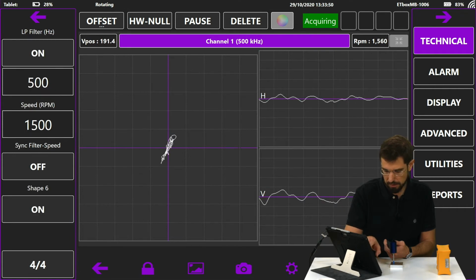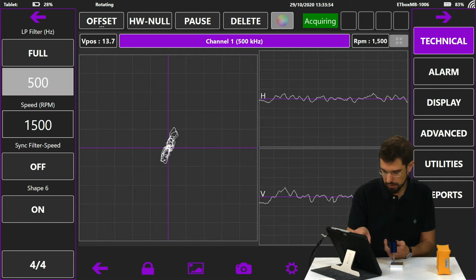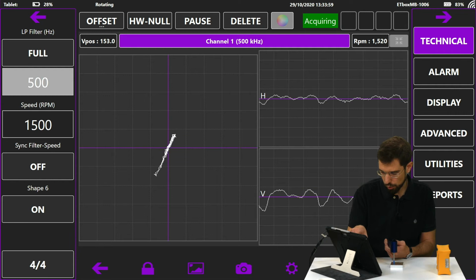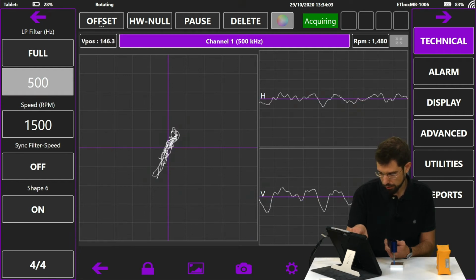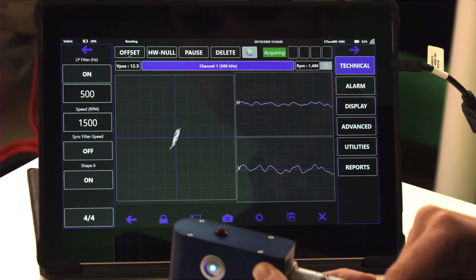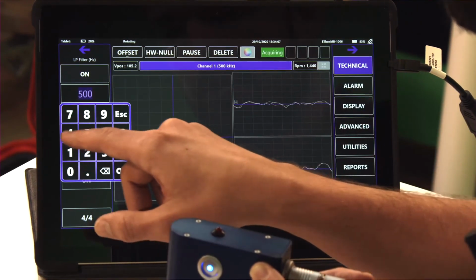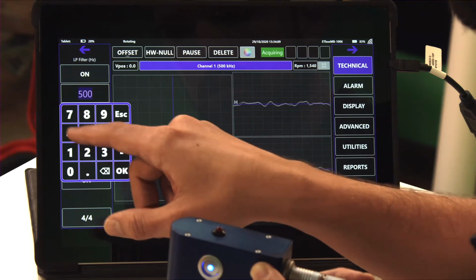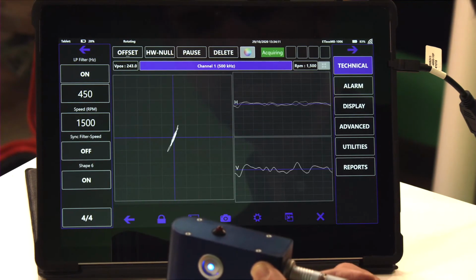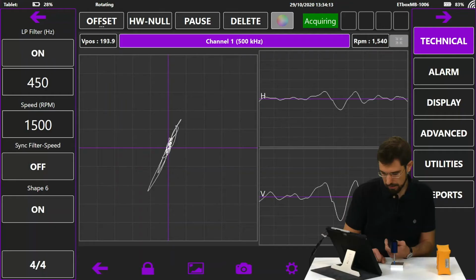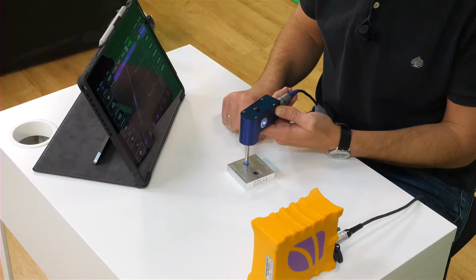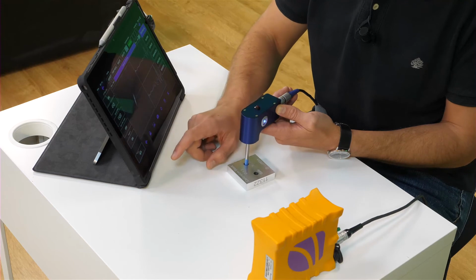On the other hand, we also have the low pass filter, which, when we turn it off, we can see that a noise comes from the motor rotation. It's an electrical noise, and once we activate it, it's filtered. We can lower it a bit. We can lower it a little bit more. And here we see it. We go into the default and we can see it.